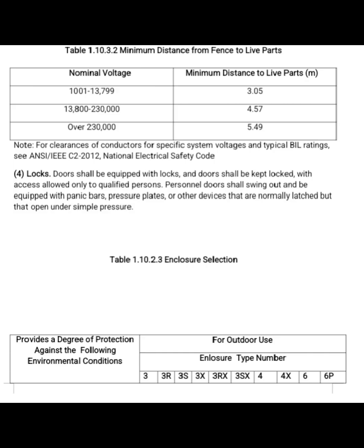4. Locks. Doors shall be equipped with locks and shall be kept locked, with access allowed only to qualified persons. Personnel doors shall swing out and be equipped with panic bars, pressure plates, or other devices that are normally latched but that open under simple pressure.